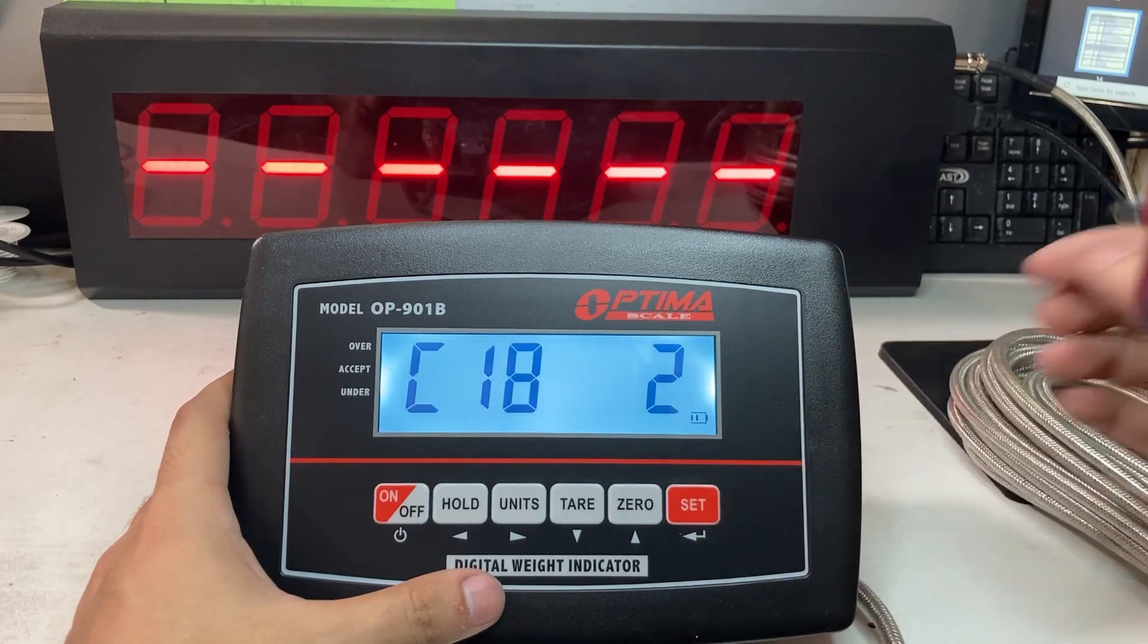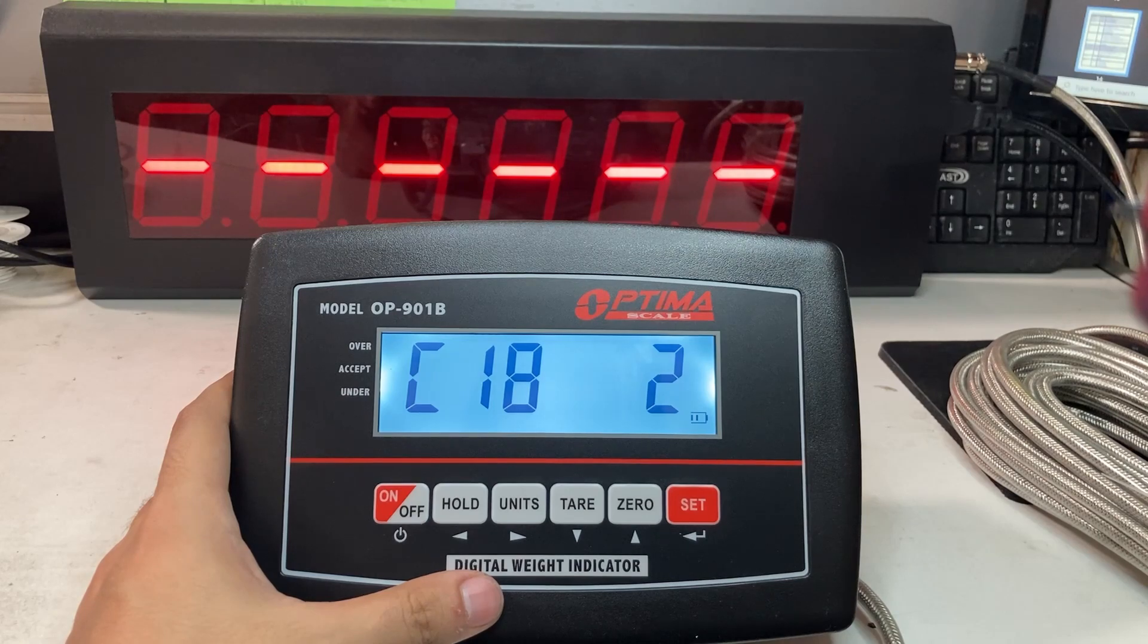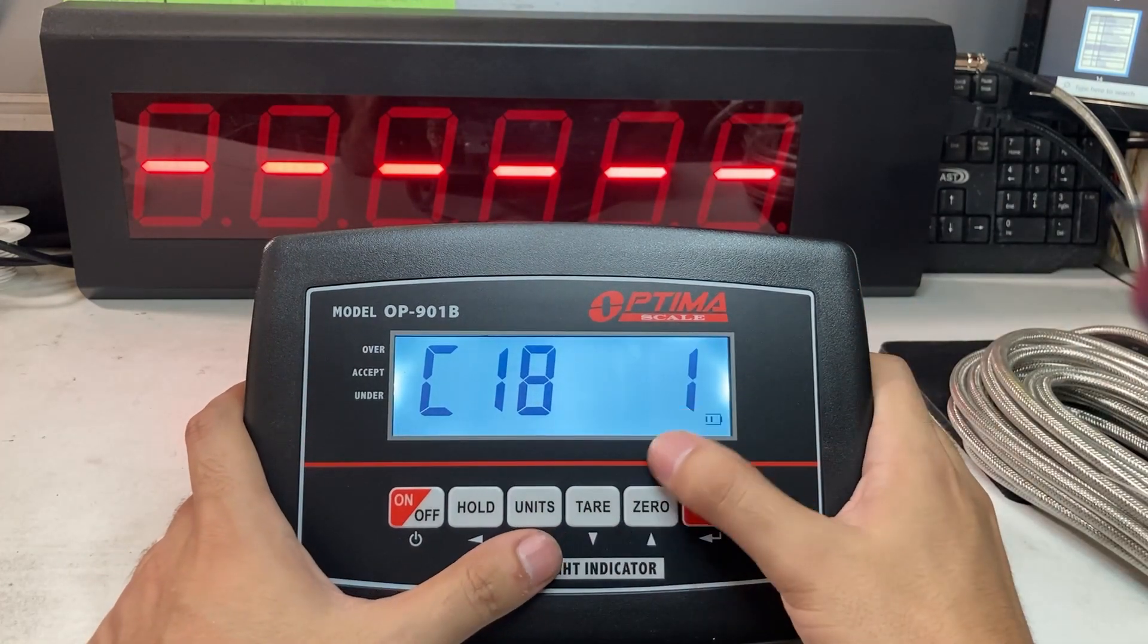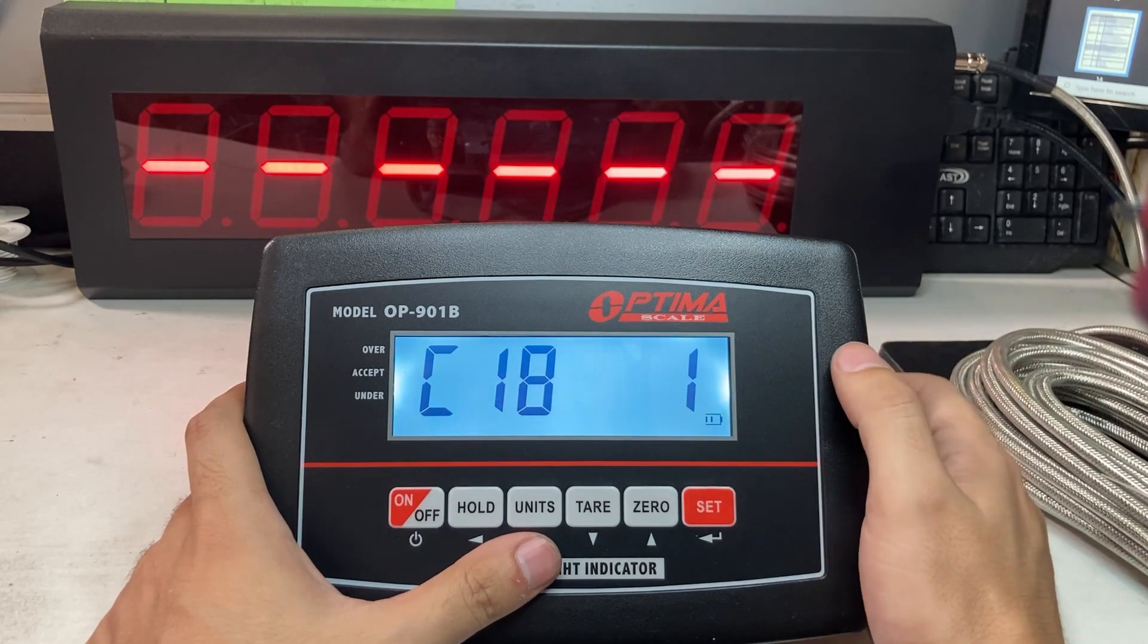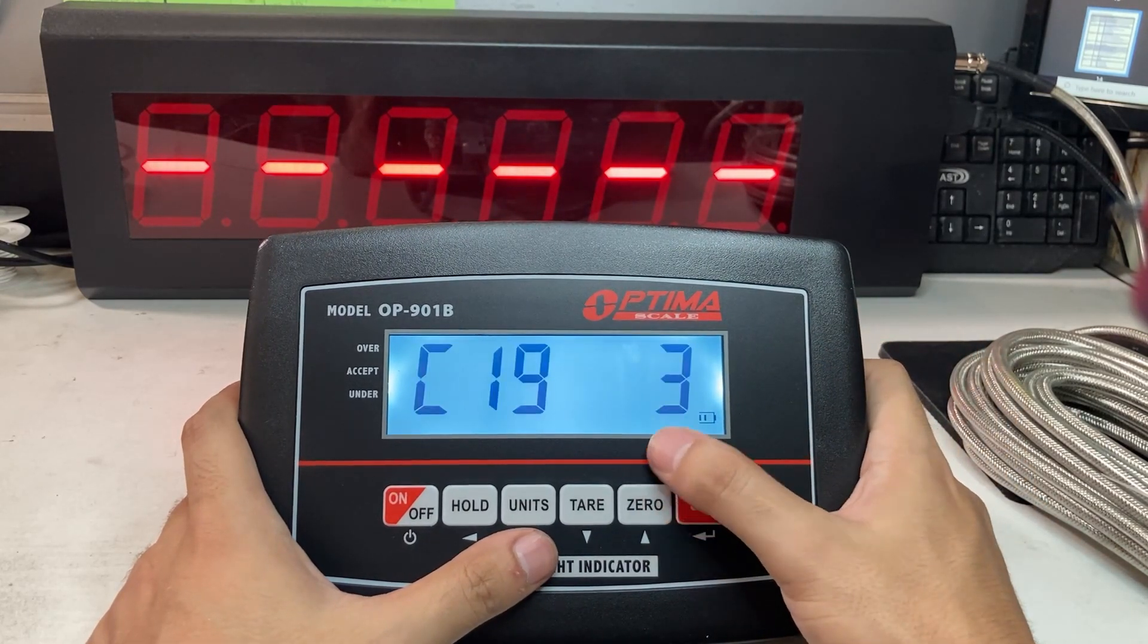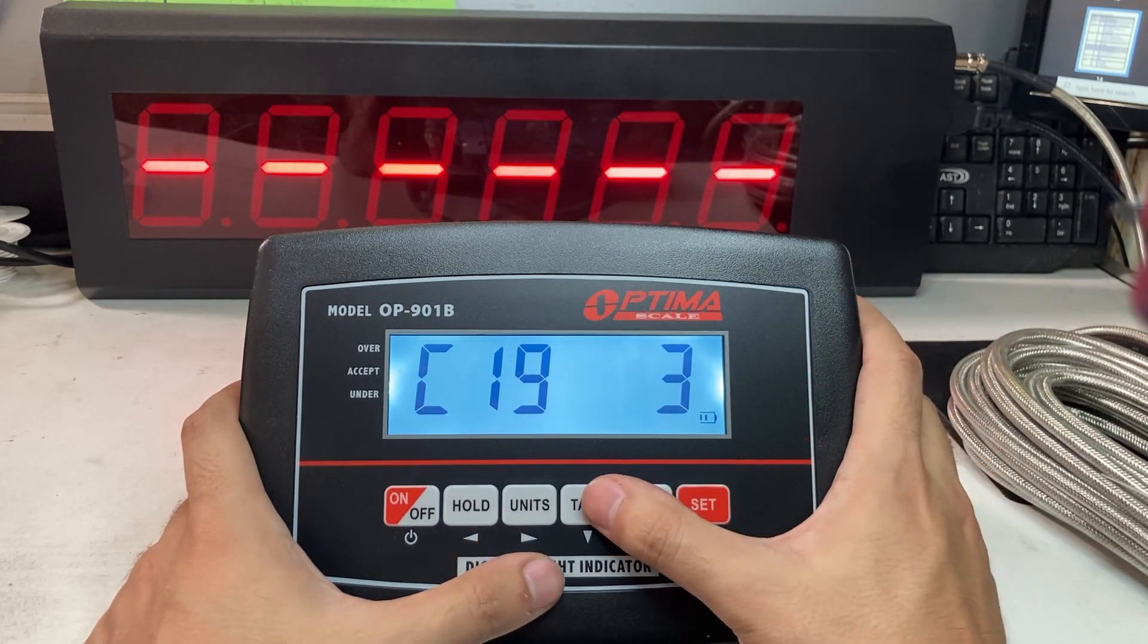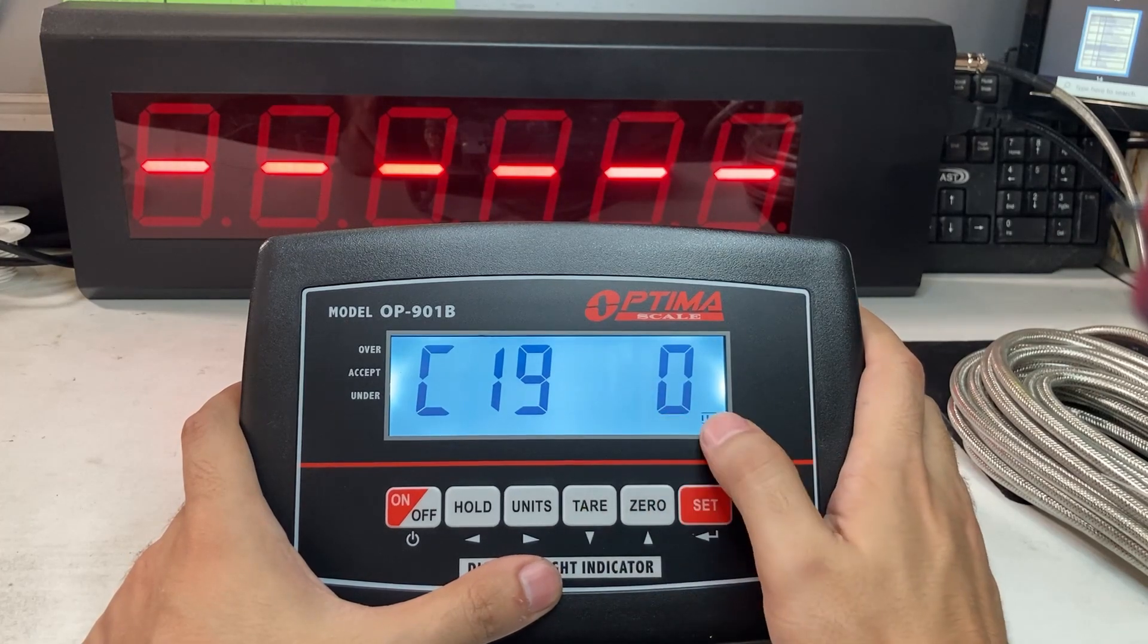Right now C18 is set to 2, so that's for a printer. We want a continuous display for like a remote display, so make that to 1. Here's in the manual. C18 to 4 would be for computer, so C18 1 right now. Then the baud rate for all our 910s are set to 1,200.